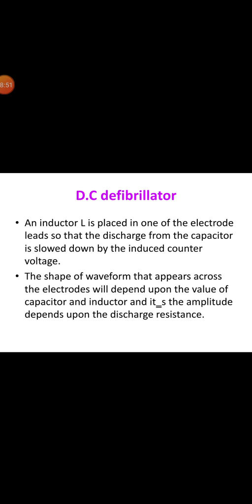and the capacitor is now discharged across the heart through the electrodes. An inductor L is placed in one of the electrode leads so that the discharge from the capacitor is slowed down by the induced counter voltage. The shape of the waveform that appears across the electrodes depends upon the value of the capacitor and inductor, and the amplitude depends upon the discharge resistance. For internal defibrillation, 100 joules of energy is required, whereas for external defibrillation, 400 joules are required. The discharge duration is from 5 to 10 milliseconds.